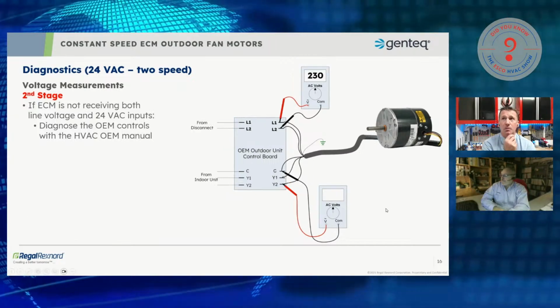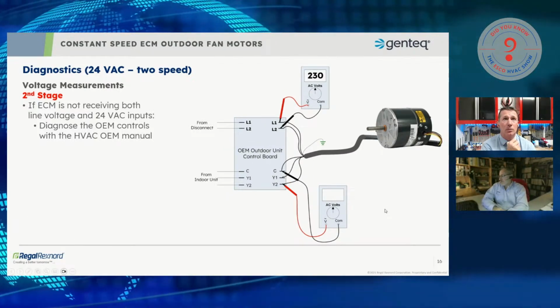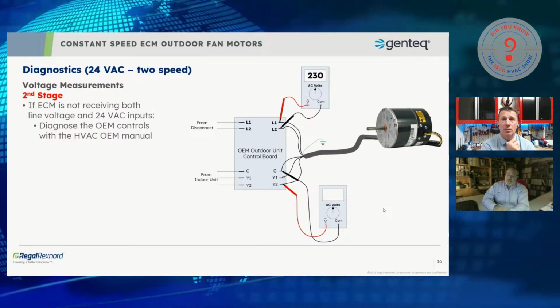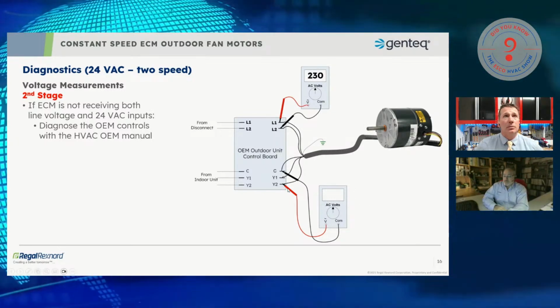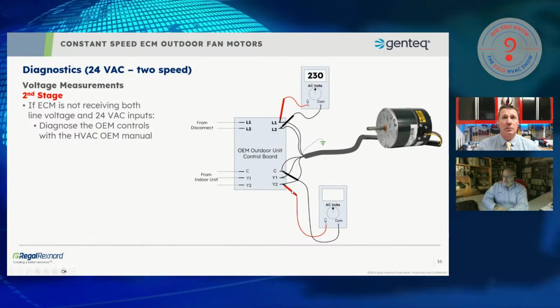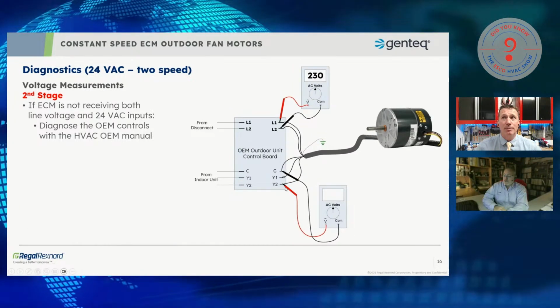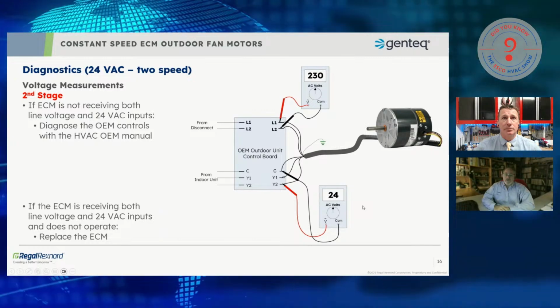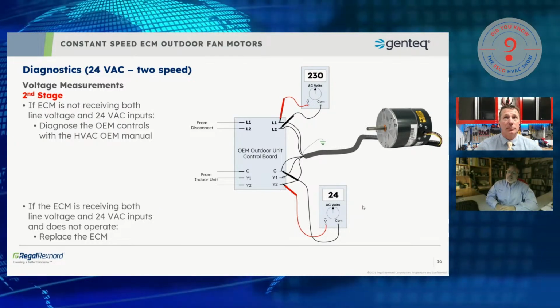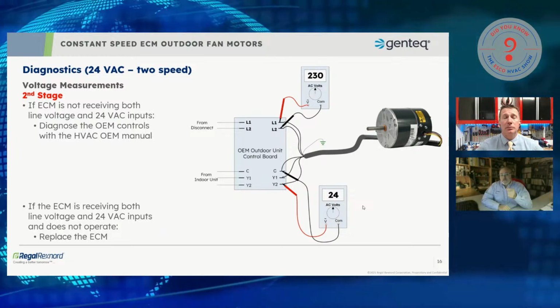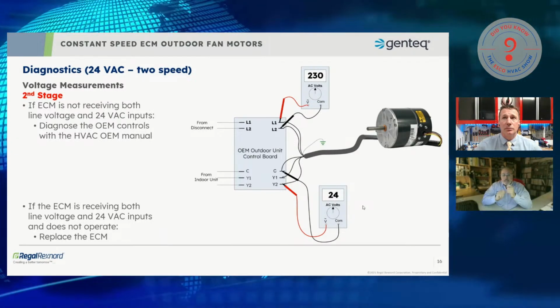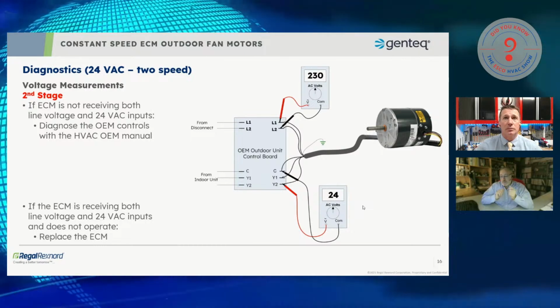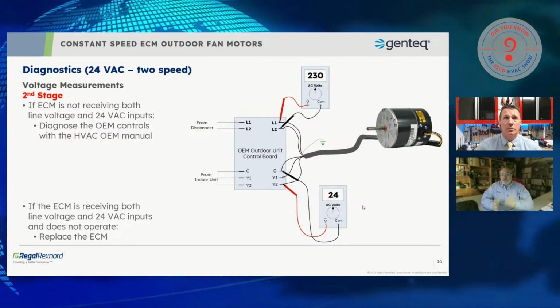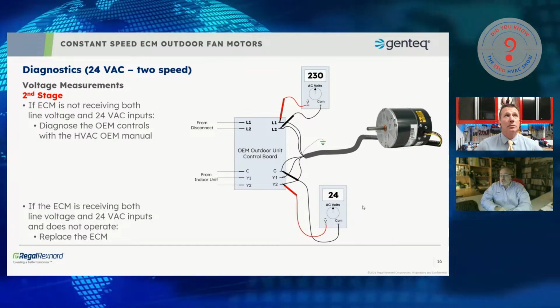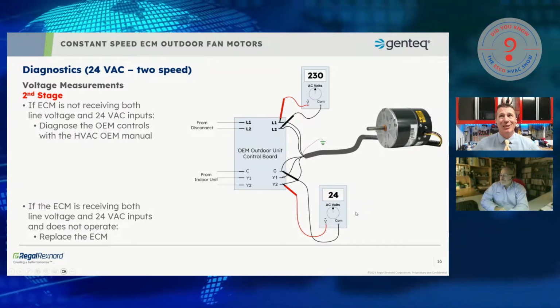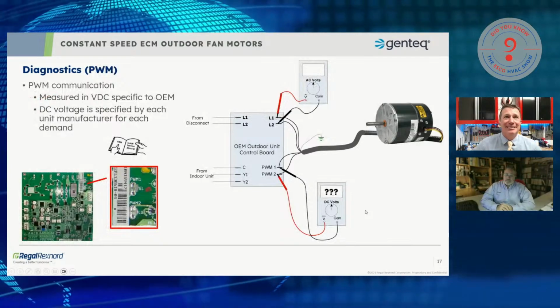So switching to second stage, we've got the same diagnostics, except you may or may not have noticed I've moved my meter over to the Y2. Again, we need both voltages for the motor to operate in Y2. And again, I'll reiterate, some systems may turn off Y1 and bring on Y2. Other systems may energize both. And on some systems, energizing both could be a third speed. So you may want to get into the manual before you start jumping terminals together, thinking it needs both of them. Great.